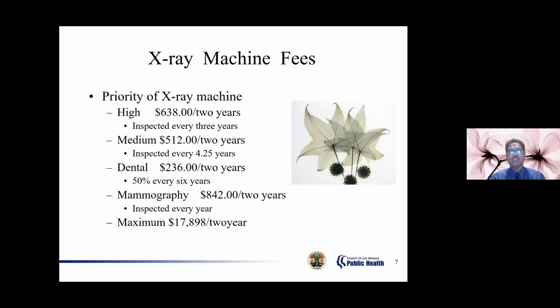Most of us, or probably all of us, have had some sort of dental X-ray. And if you notice, dental units are mainly just one kVp unit. They're usually around 65 kVp, 70 maybe, but usually around 65. The only variation you have is exposure time, really, because the mA is fixed and the kVp is fixed. There's very little variation in dental exposures anyway, because even though teeth are one of the hardest, most mineralized parts of our body, the 65 kVp range is sufficient.